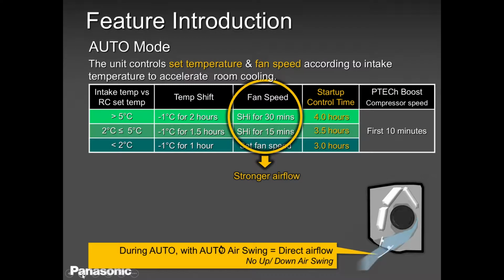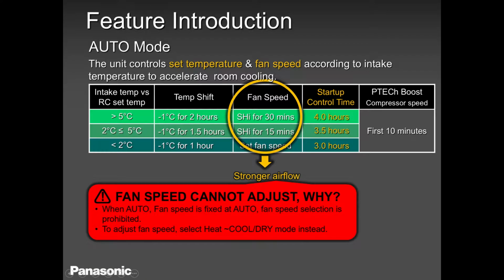So in auto mode, the fan speed is the auto fan. Just to correct myself, not auto mode, but in auto fan, the fan is regulated based on the temperature of the coil. Auto mode, as I mentioned earlier, changes from cool to heat, heat to cool. Auto fan runs high or low depending on the temperature of the coil.